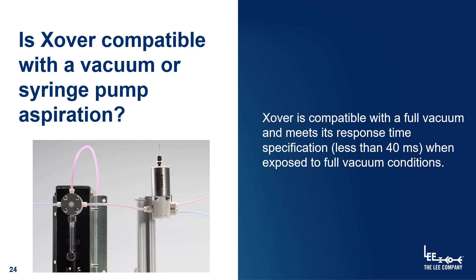A common concern with pinch tube style valves is whether they will get stuck open or closed when exposed to vacuum conditions. The most common source of this concern is when aspirating with a syringe pump, which can cavitate fluids and create a strong vacuum. I'm happy to report that Crossover is capable of handling a full vacuum throughout its life — the valve can open and close quickly and efficiently.